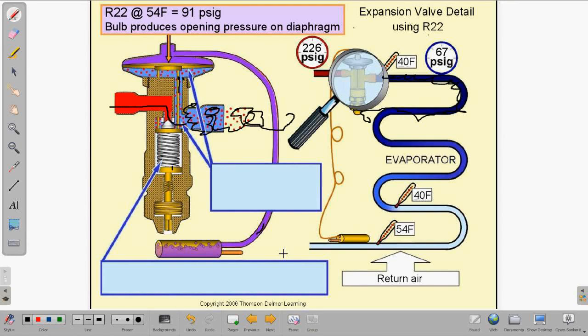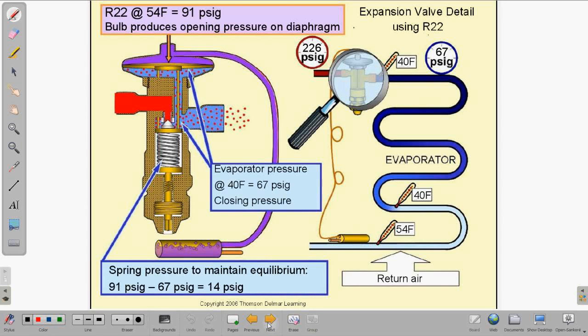Now remember, if you want to check to see if this is operating properly, you can take that valve off and drop it in a warm glass of water. It's going to apply maximum amount of opening force on the diaphragm if there's refrigerant in here, and you should see that ice begin to go away if this valve is working properly. All right, hopefully that makes sense for everybody.